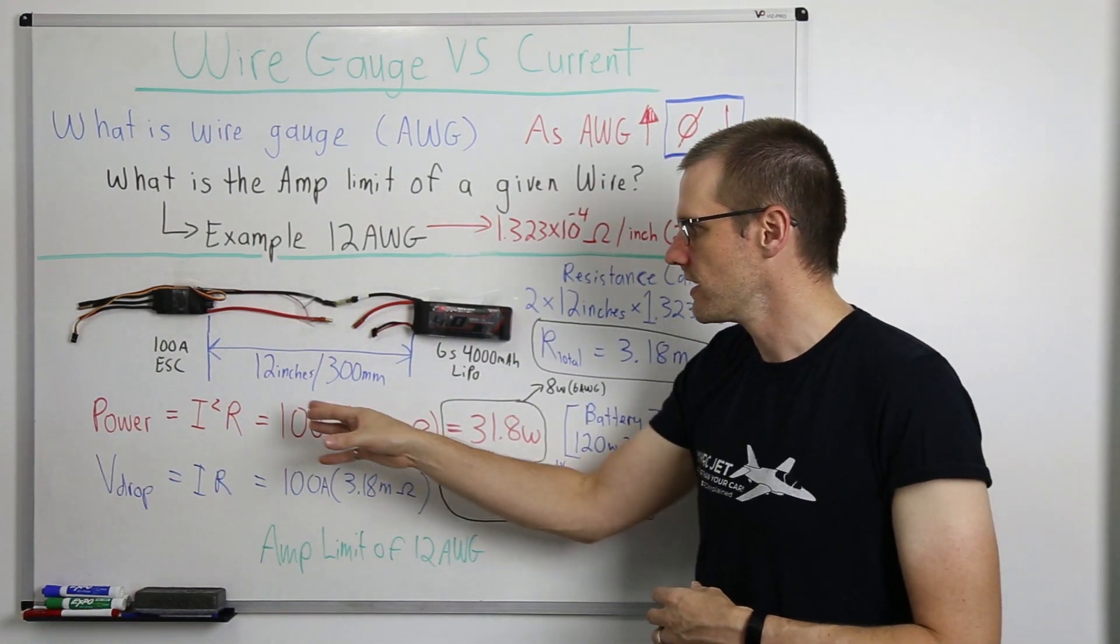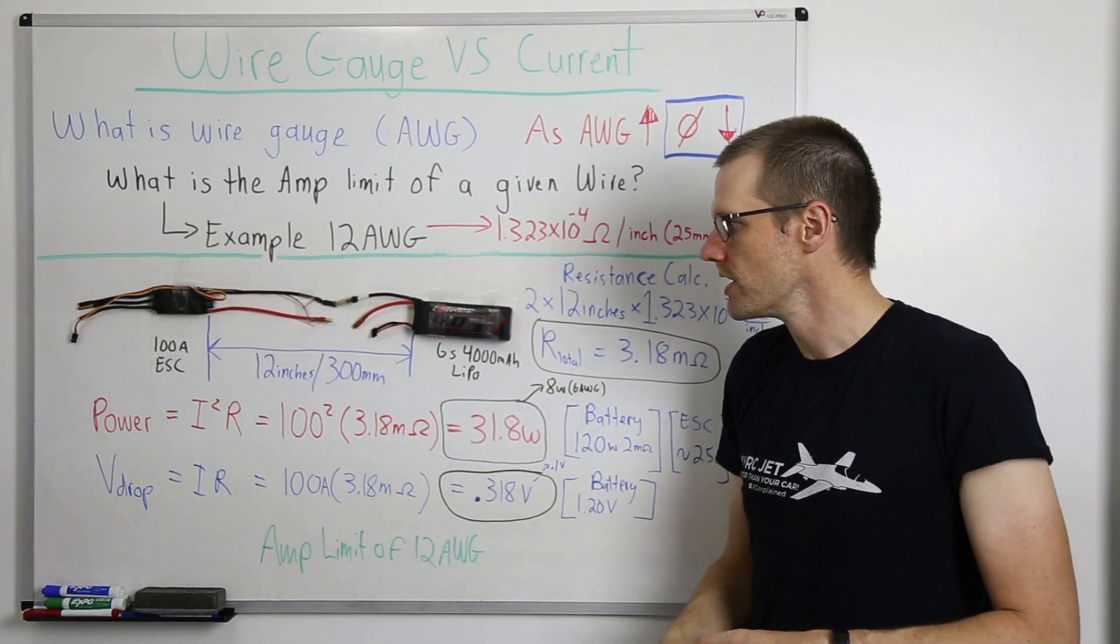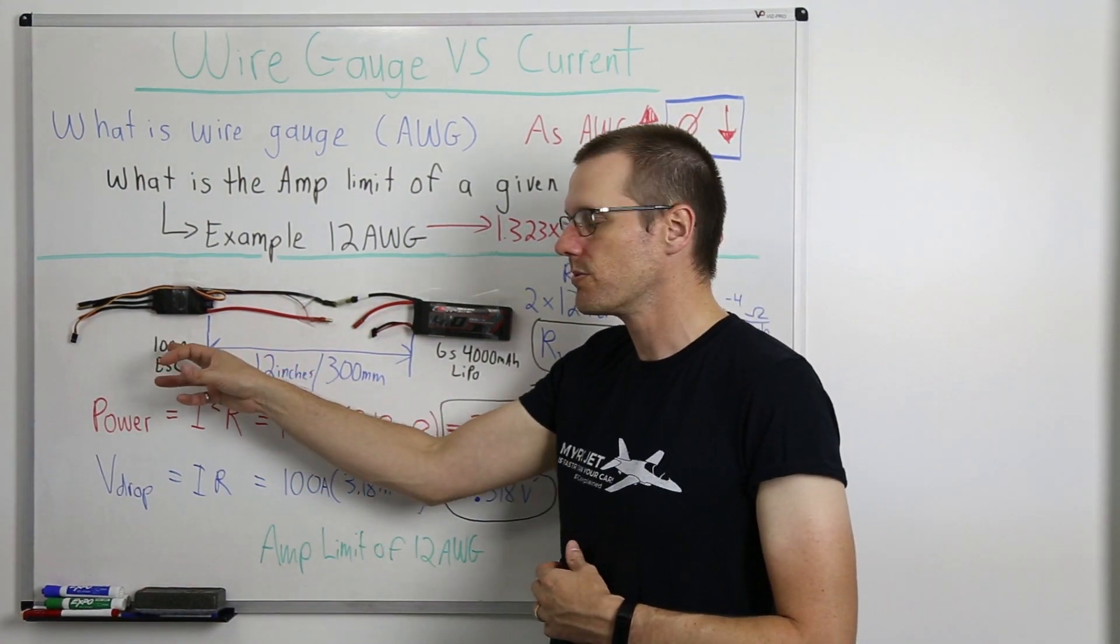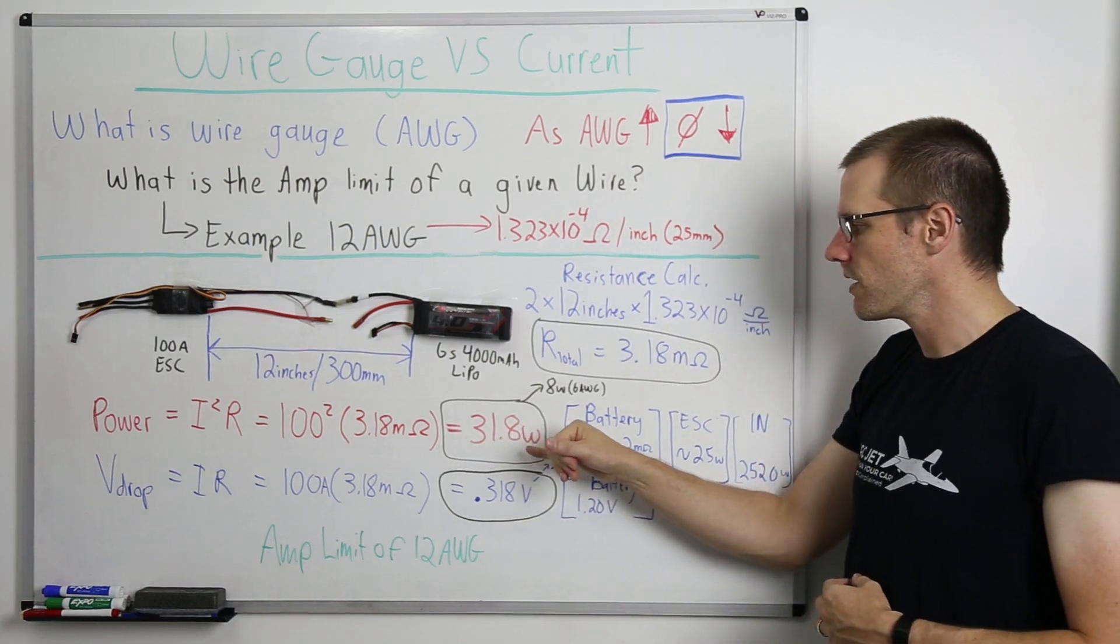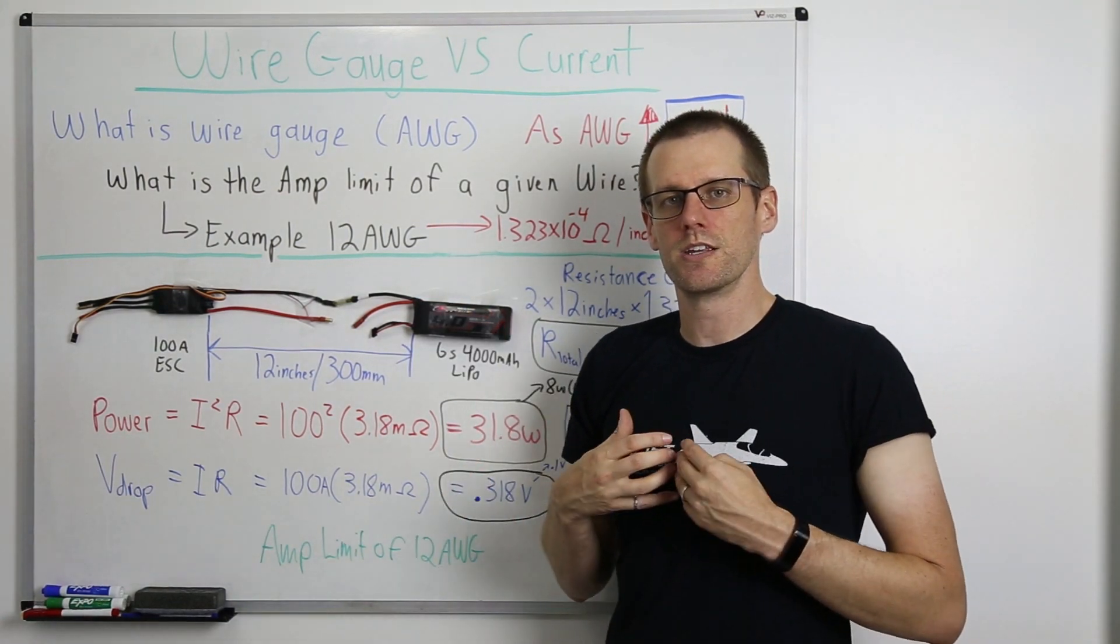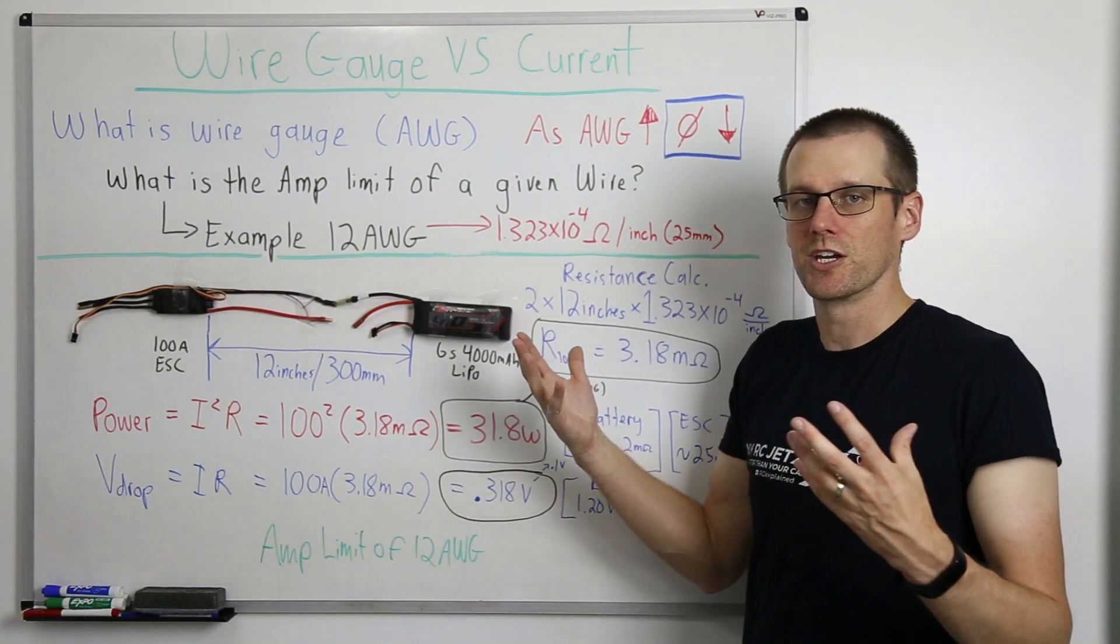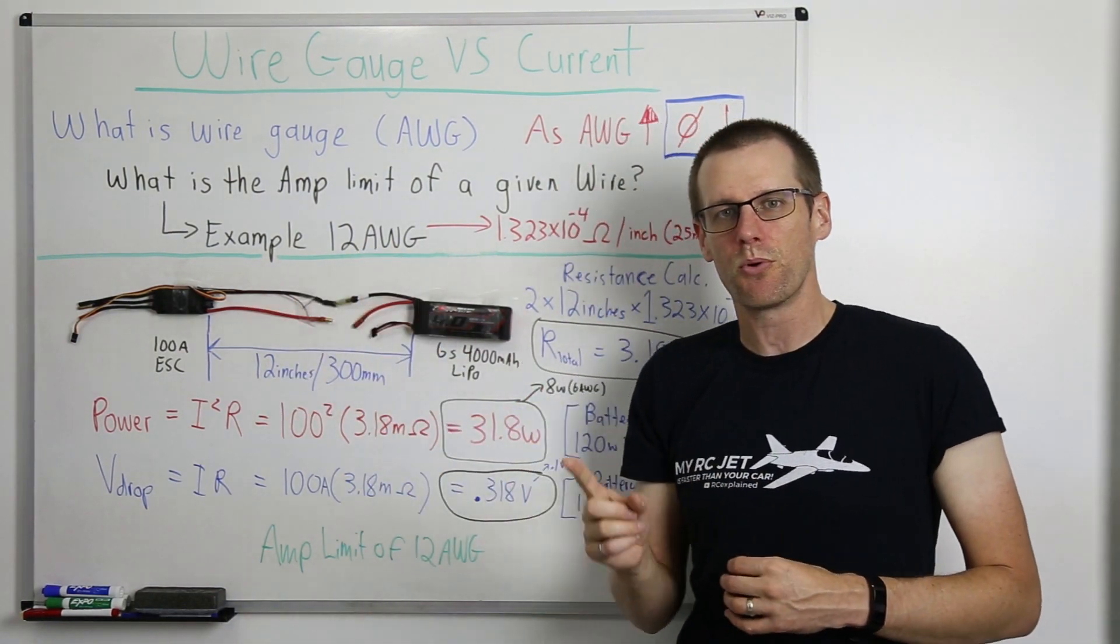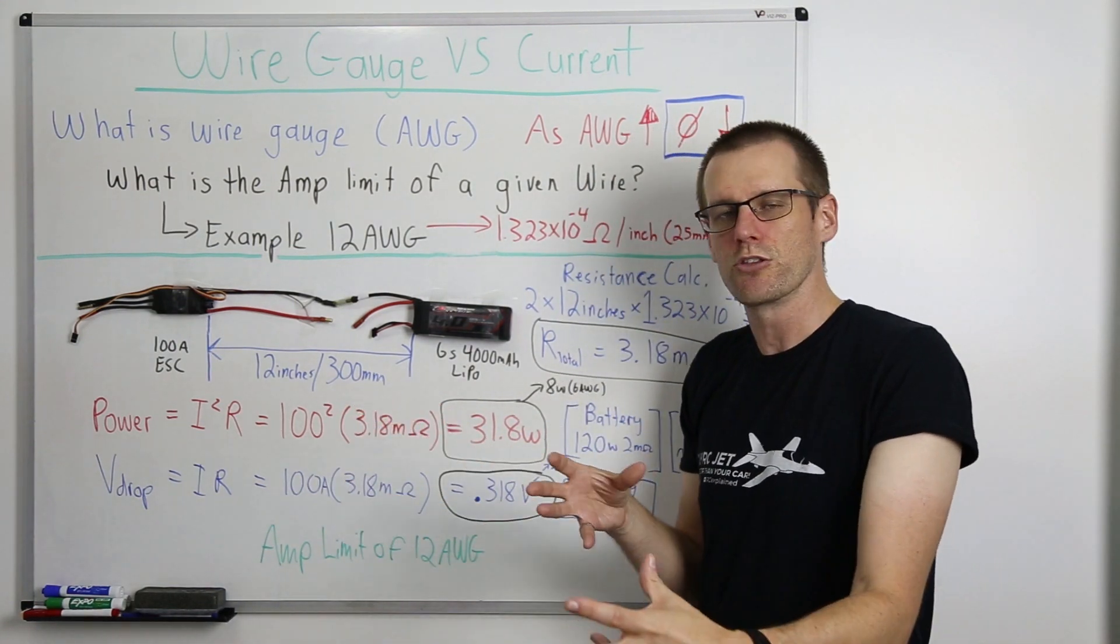So now we're going to go and jump into our first calculation and look at exactly what happens to power. So the formula to determine power and we're looking at what kind of power losses do we get out of these wires is going to be the current squared multiplied by the resistance. Here we get the current of 100 amps that we talked about in our example with this 100 amp speed control. We square that, we multiply it by 3.18 times 10 to the negative 3, and we get 31.8 watts of power being wasted essentially from those wires. Those wires really ultimately need to go and get rid of those 30 watts so that it does not overheat. If it can't get rid of those 30 watts, it'll increase in temperature until something could possibly burn up.